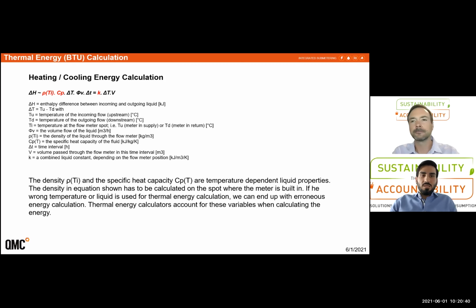BAS systems take volume and temperatures from flow meters and temperature sensors and typically use a constant factor to calculate energy, whereas thermal meters take the density and specific heat capacity of the liquid at the measurement point to do this calculation. Using a constant factor throughout the operating range of, let's say, 5 to 75 degrees C in a hydronic system could result in somewhere between 3 to 5% additional uncertainty in the reported energy value. Typically, an energy management system or a BAS uses a constant factor as opposed to the calculated factor to calculate the thermal energy. Next slide, please.